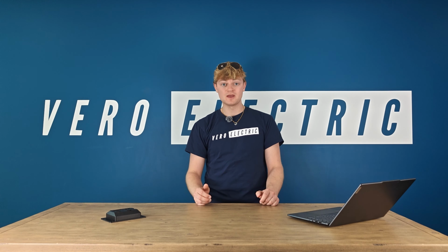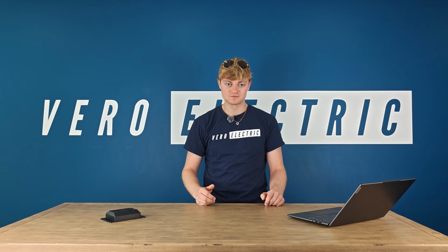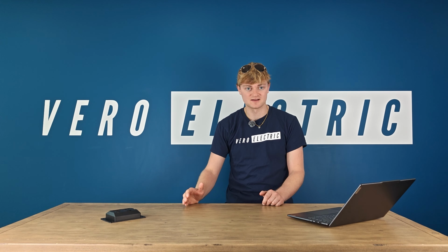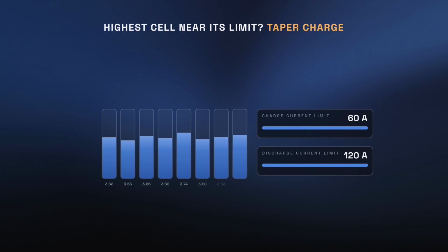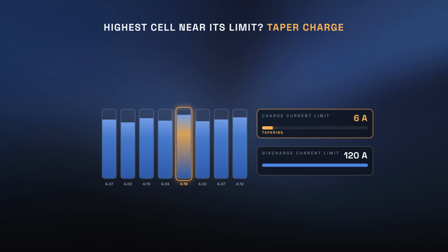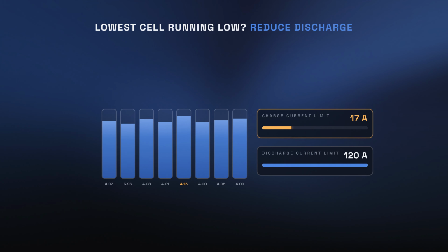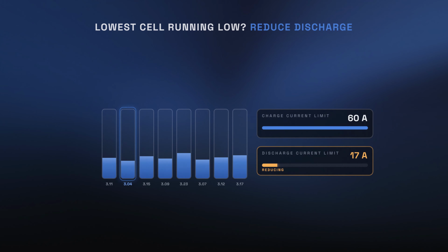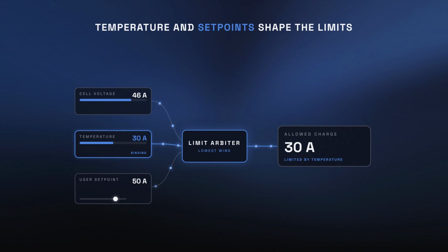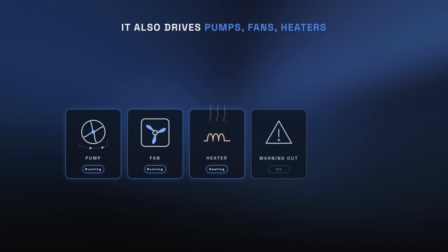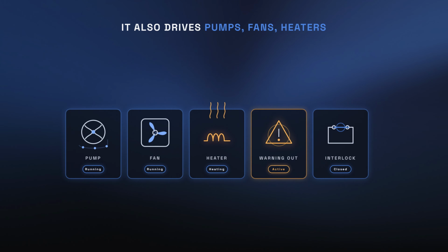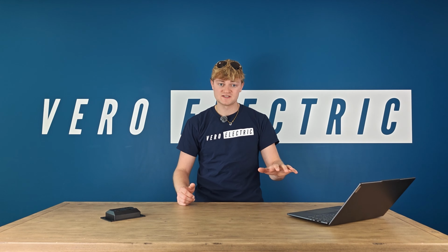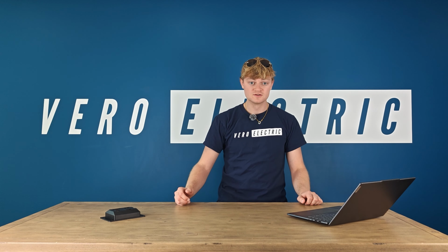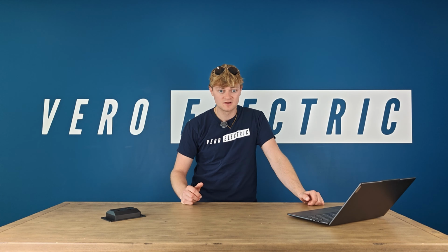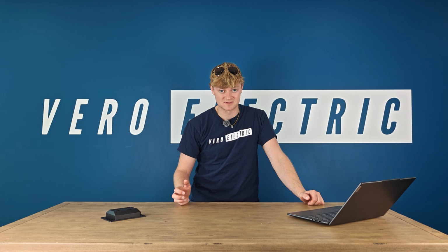During operation, the BMS may command the charger or inverter to reduce current instead of immediately opening the contactors. As the highest cell approaches its upper limit, the BMS can taper charge current. If the lowest cell is running out of juice, it can reduce discharge current. Additional factors like temperature and user set points also contribute to these limits. Additionally, the BMS may control pumps, fans, heaters, warning outputs, and interlocks in some setups. A hard shutdown is the last line of control, used when continuing to operate would be unsafe or when another device ignores the BMS limits.